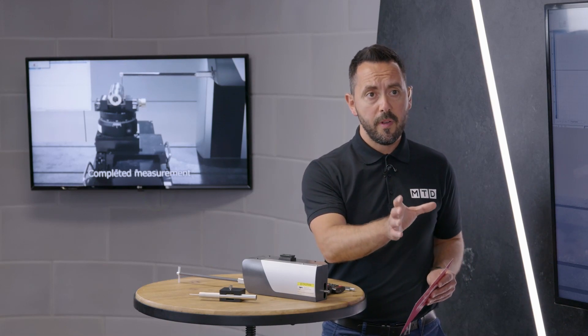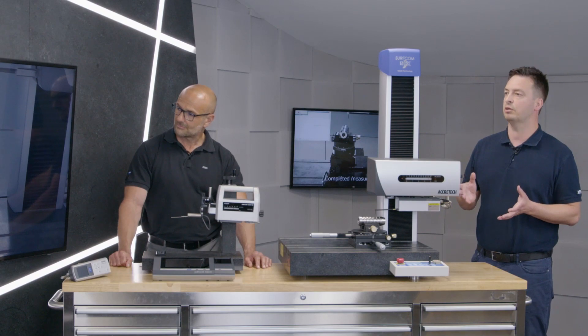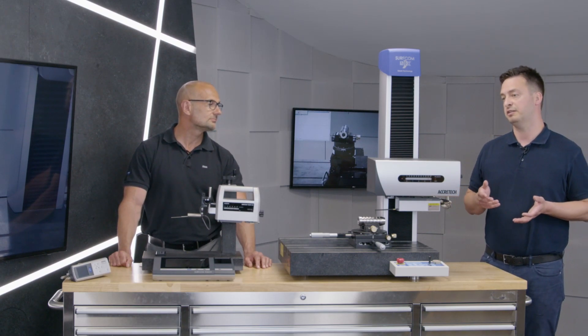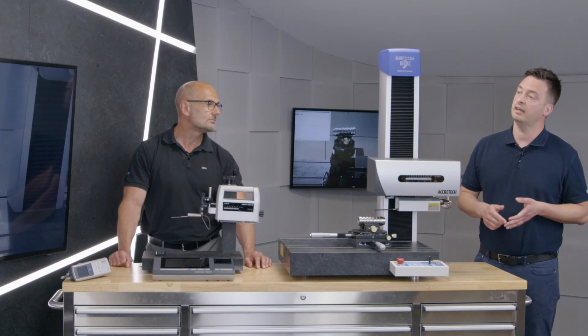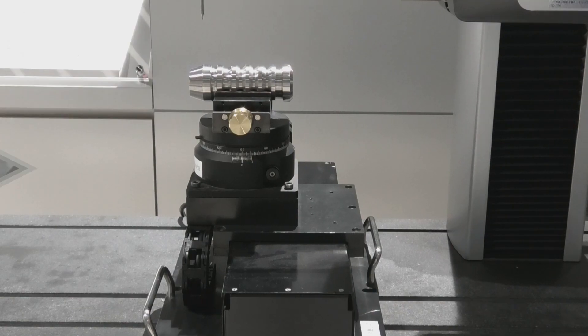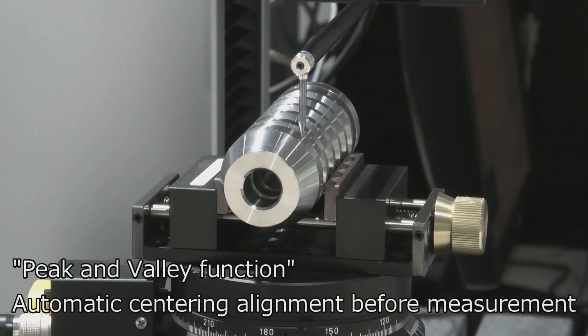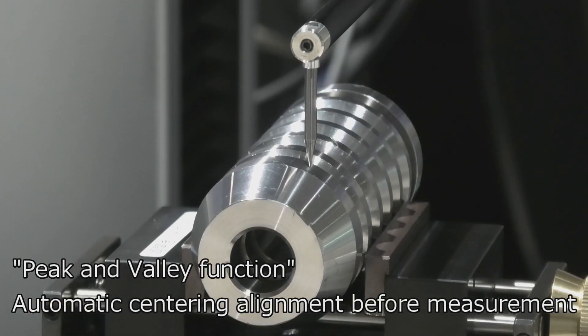And that's not the only world first this product offers. The Next platform comes with five detectors: a dedicated high-resolution roughness detector, a standard and high-resolution contour detector, an optical detector, and also a hybrid detector — another Accretech world first, patented technology — which gives truly simultaneous surface roughness and contour measurement in one pass.